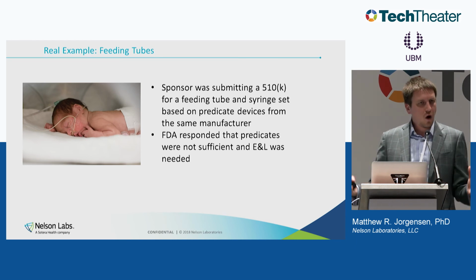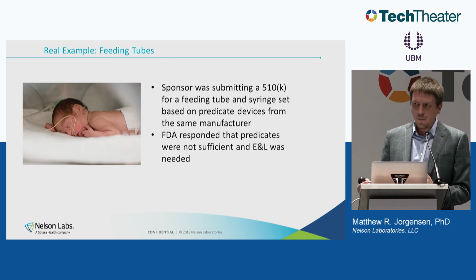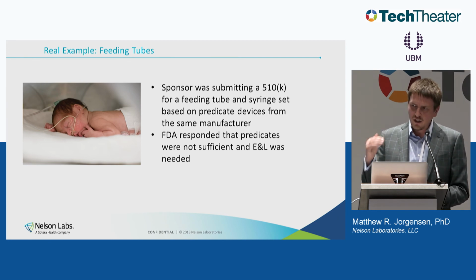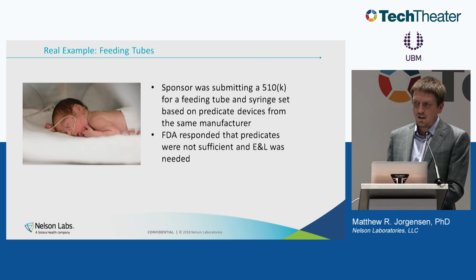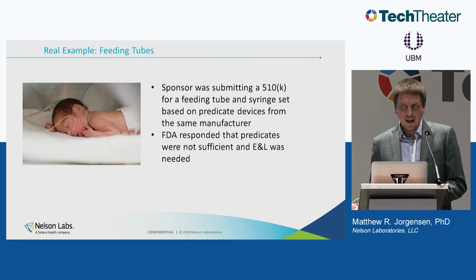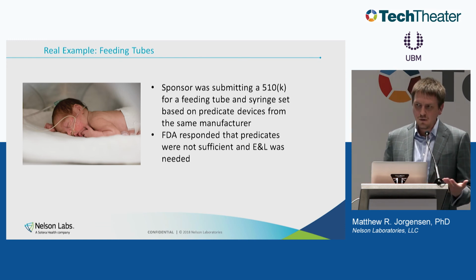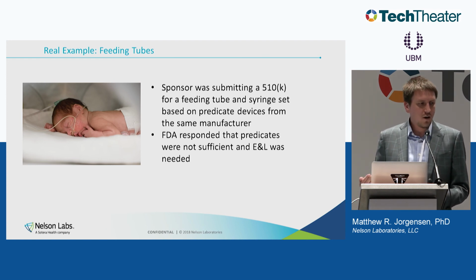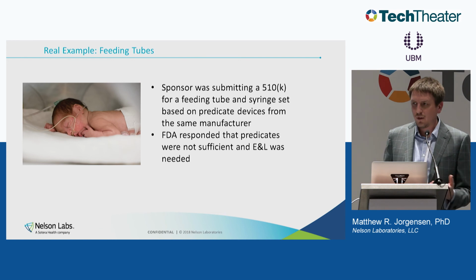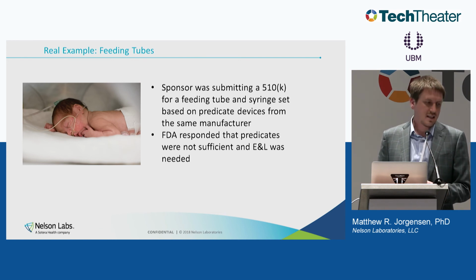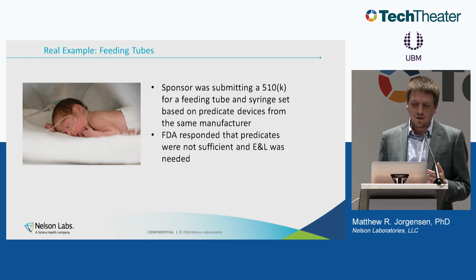They had gone through the whole process of doing the biocompatibility tests per 10993-1. They just checked the boxes, did all the tests, and passed. So they submitted this whole docket to the FDA, and the FDA said, okay, great, this is nice, and we understand that biocompatibility tests, including the ones you conducted, are on adult animals, not underweight developing animals, and we don't really find animal tests to be adequate in this case. So they kicked it back, came to us, and the FDA recommended chemistry and a toxicological risk assessment. So that was the setup here.